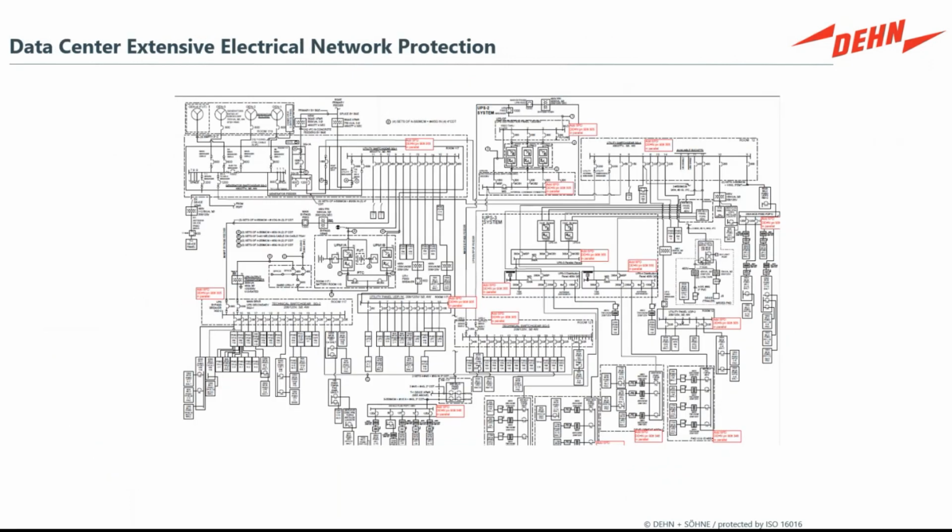But the application of lightning protection around the structure isn't enough. You still have to pay a great deal of attention to surge protection devices, to the electrical protection around things like transfer switches at secondary and tertiary load center panels that might be feeding the lamps out in the luminaires out in the parking lot. You want to prevent that energy from coming back into the circuit. You want to have lightning protection and surge protection embedded around the battery backup systems and your inverter converter systems. So it's not just that you applied a single SPD at the service entrance.